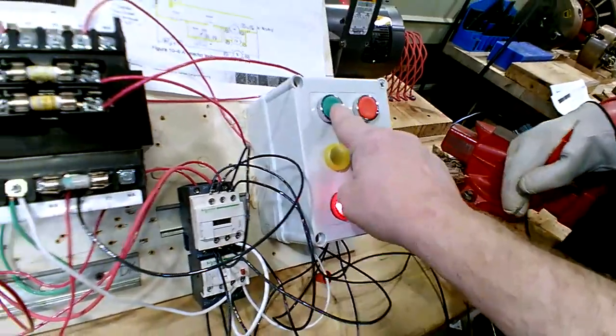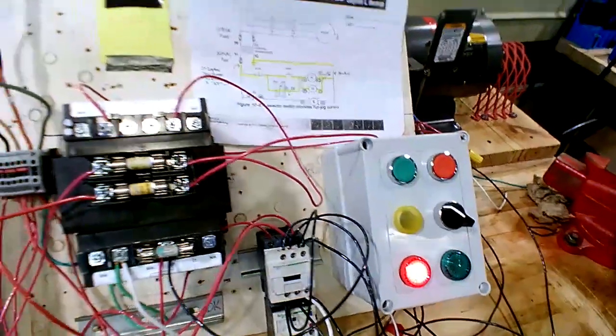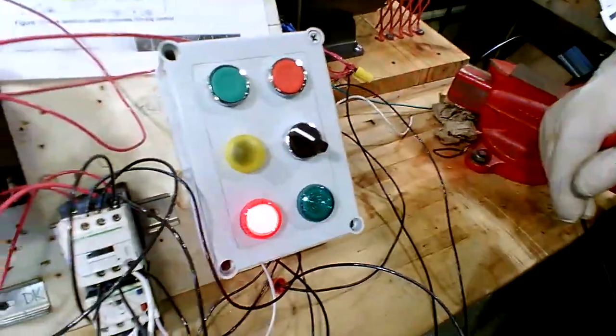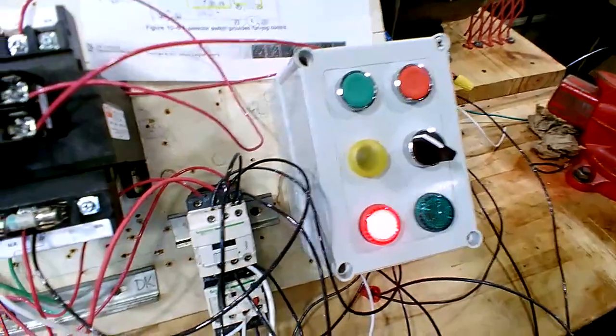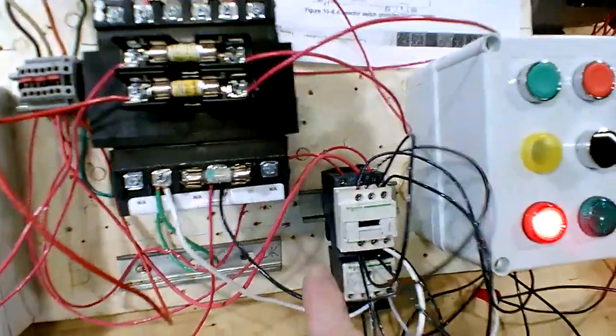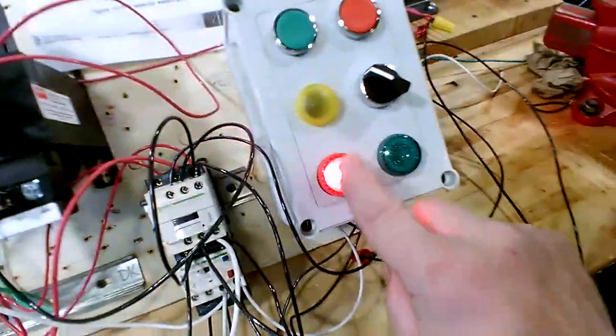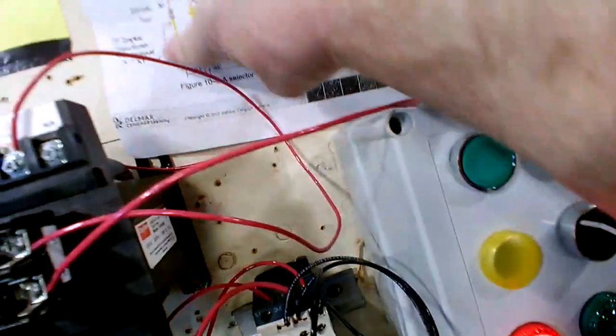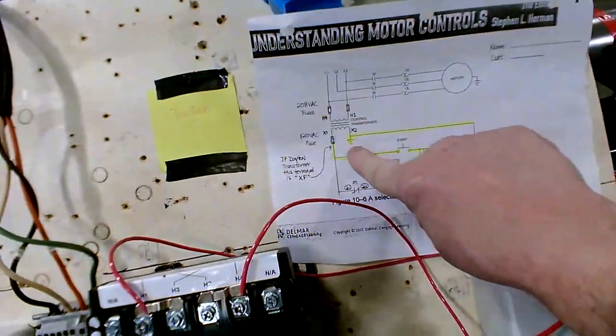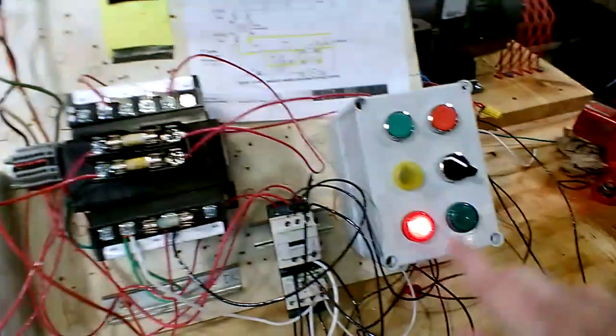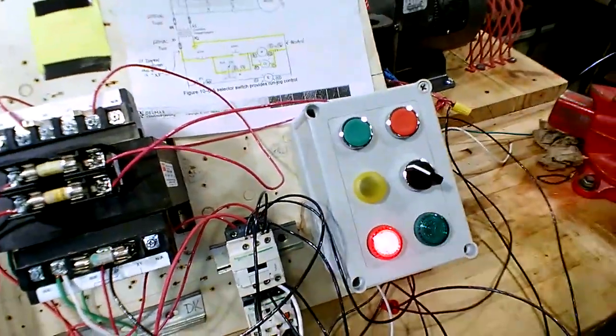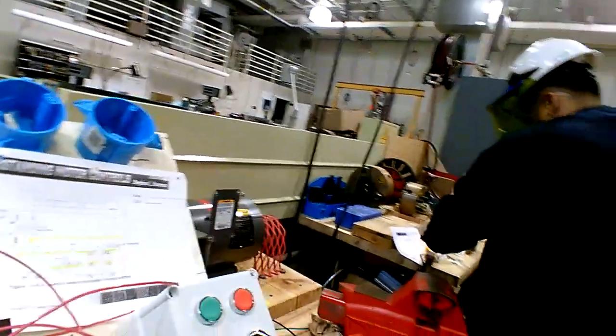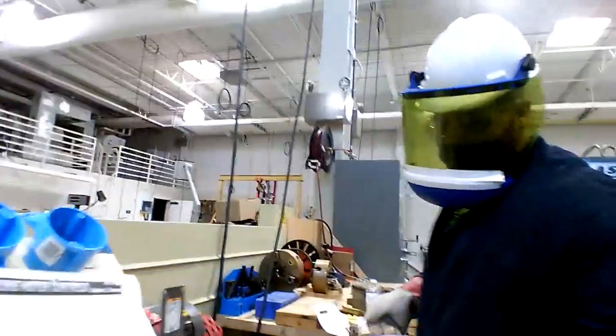That start button is never really getting to the coil, which I'm going to guess is probably a wire that popped off inside that panel. Wouldn't you think so? That's what I'm guessing, because we know we've got that 120 and that red light, so that's telling you that you've got it there. But you're missing it in this section. So I'd say let's lock it out, open up the panel, and let's see what we've got. I think you're getting ready to find it right quick here. So we'll lock this thing out.